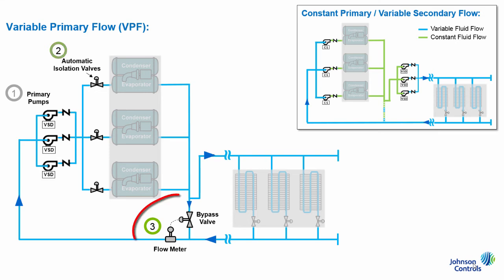And thirdly, we have our bypass valve and associated flow meter. The primary purpose of this duo is simply to maintain the required minimum flow rate through any operating chillers. In other words, based on the system load, the controls could tell the valve to open and allow fluid to bypass the coils to feed the chillers. This approach is compared to a primary-secondary system, where again there is a common pipe as shown, but no flow regulation, meaning fluid is able to flow in either direction to balance the system. However, the unwritten rule with this design is that the primary flow should always be equal to or greater than the secondary flow for optimal performance. Therefore, the flow would follow the same path as a VPF system.